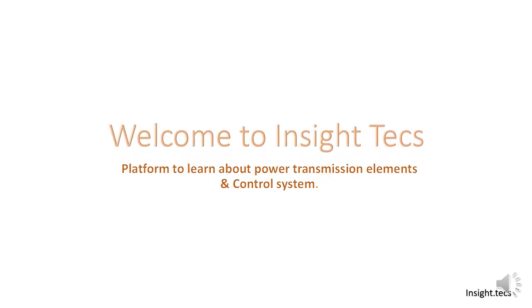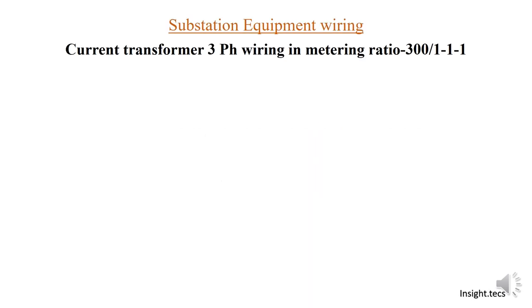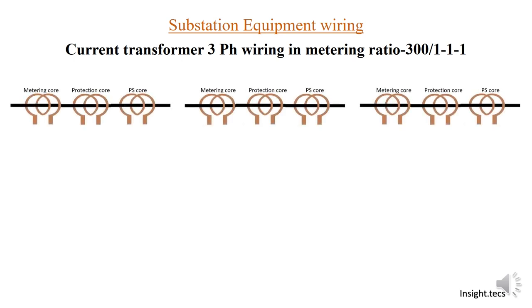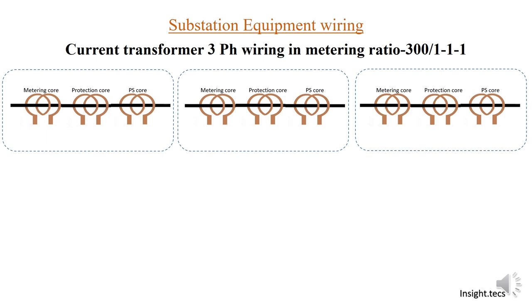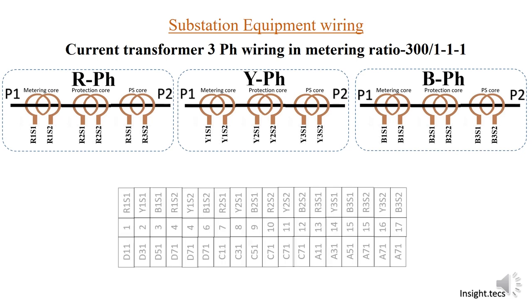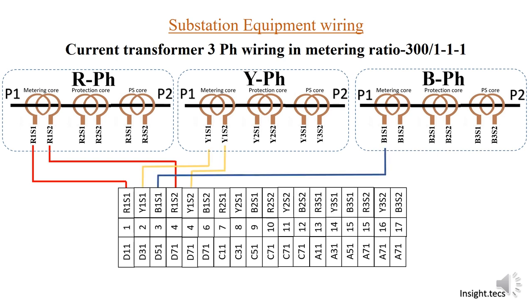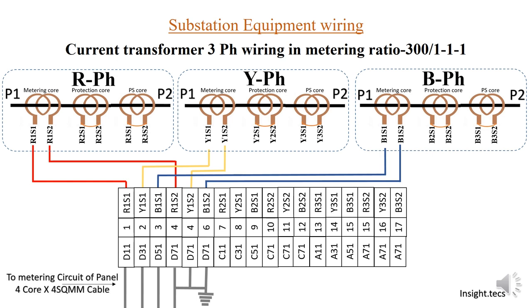Hello friends, welcome to Insight Tecs, a platform to learn about power transmission elements and its control system. In the previous video we saw how the current transformer three-phase wiring is done with a metering ratio of 300/1. Let us recollect that using this animated diagram — here we have R, Y, and B phase connected for metering, with four wires coming out: d11, d31, d51, and d71. All these four wires go to the metering circuit in the panel using a four-core, four-square-mm cable.